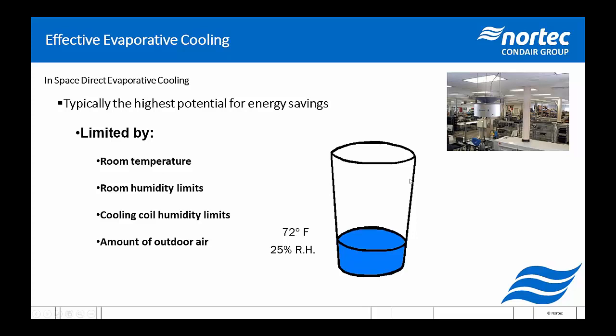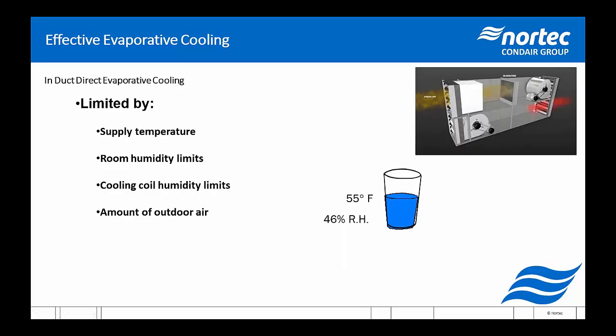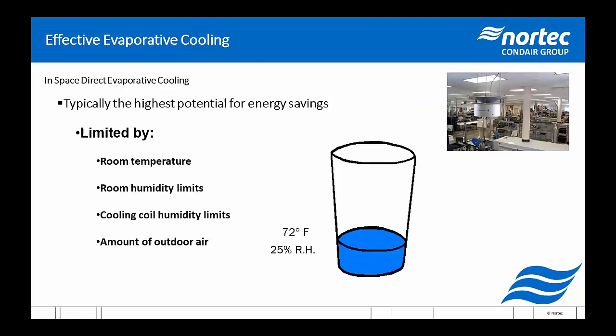If we look at in-duct evaporative cooling, where we're cooling and humidifying directly inside the air handler, then typically we've got a supply temperature of about 55 degrees, and this 46% RH is the exact same amount of water as this 72 degrees and 25% RH. So that's where we can see greater savings with the in-space direct evaporative cooling. Generally, we see in-space applied in factories and warehouses and places with larger ceiling heights, but we're seeing it more and more in even as low as 10 feet or 8-foot ceilings in smaller commercial type applications.